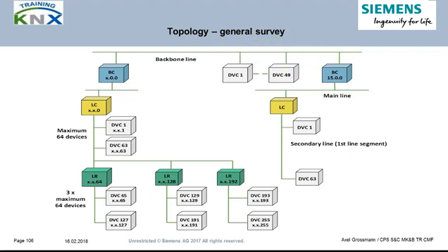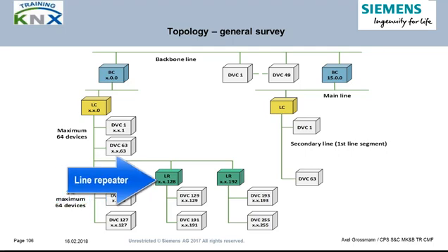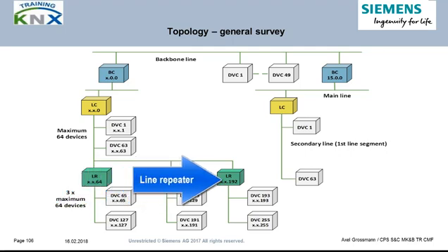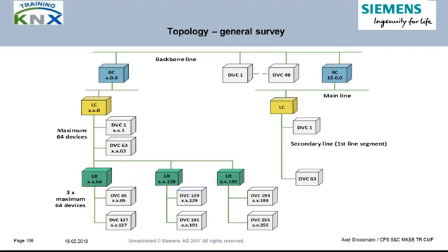All area couplers are linked with each other via the backbone or area line. If no other solutions upwards or parallel are possible, lines can also be extended downwards. For this extension, a so-called line repeater is required. Three line repeaters per line are permitted, connecting the same number of line segments to the first one. Addressing, device number limitations, and the disadvantages of line repeaters will be explained on the following pages.